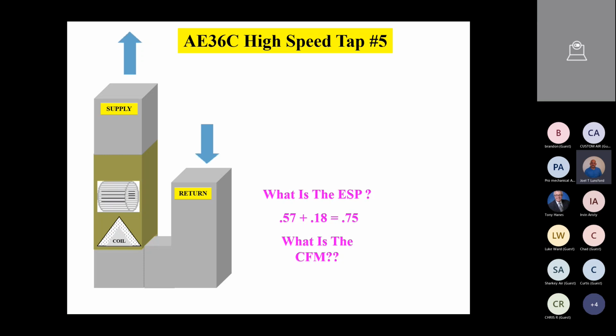At 0.75 inches static, what is the CFM on that AE36 air handler on a high speed tap? 0.75. Anybody, go ahead and unmute your mic and let me know what the airflow is on this final example.